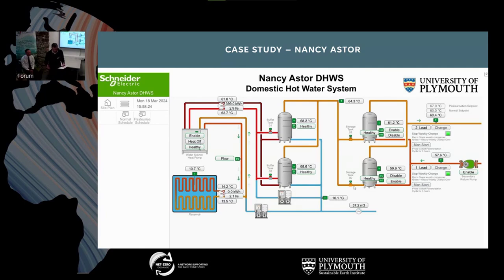So we explored several options with a view to operate the system at a lower temperature. We looked at using chlorine dioxide dosing and alternative silver copper ionization treatments. However, the capital cost was really high, maintenance costs were really high as well, and it was eventually concluded that we needed to boost the temperature using direct electrical input to take care of the final few degrees.